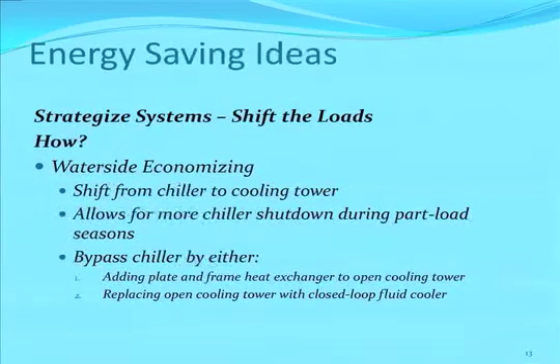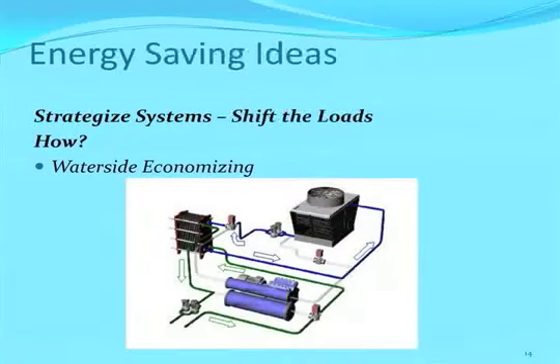Next, water side economizing. Here you're shifting chiller load to the cooling tower, and it can let you shut down your chiller some of the time during part load seasons. There are two ways to do that. You can add a plate and frame heat exchanger to an open cooling tower or replace the cooling tower with a closed loop fluid cooler. Here's an example of the plate and frame heat exchanger here in between your chilled water, so bypassing the chiller where you can and then rejecting that heat via the cooling tower.